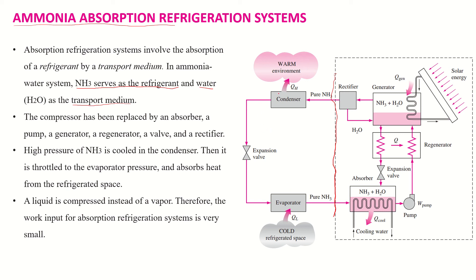In the absorption cycle, the compressor is replaced by an absorber, pump, expansion valve, regenerator, rectifier, and a generator. At the start of the cycle, a liquid is compressed instead of a vapor. This means the pump is used to increase the pressure of the liquid, whereas a compressor is used for vapors.